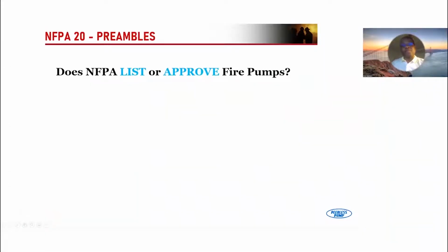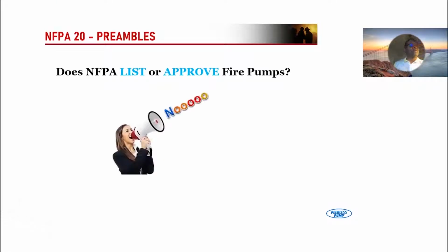Another thing I wanted to touch on: does NFPA itself list or approve fire pumps? The answer is no, they do not. This is left to an independent authority to interpret the NFPA 20 'Bible' and make sure the pump manufacturer or packager complies with its requirements.